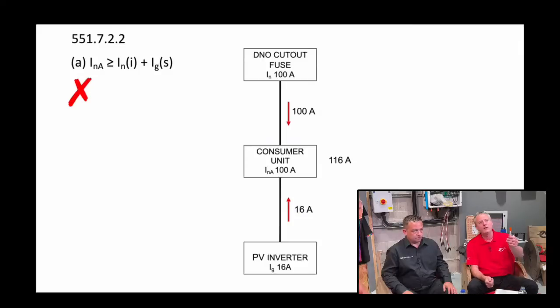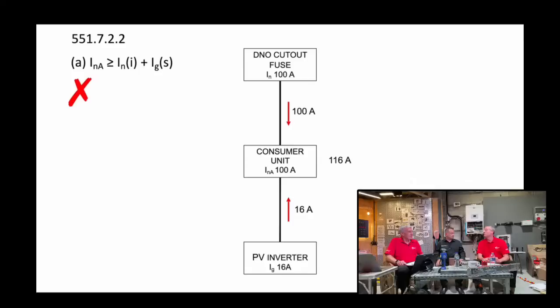Now, what if you're in a really lucky position? I've got a friend who had a 100 amp fuse, and then when they installed his smart meter they took the 100 amp away and put an 80 in. So if I replace that with 80, and this gentleman might be lucky enough to have solar, he'd be right, wouldn't he? It's absolutely fine. Come up roses, yeah, there's no problem with that at all. But that's not the usual scenario - we want more current, not less, don't we?